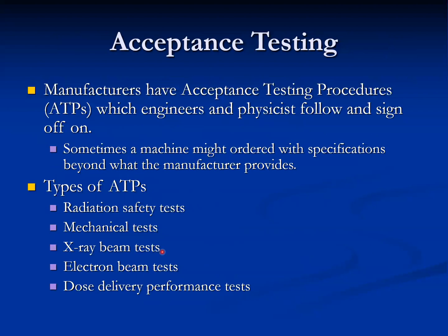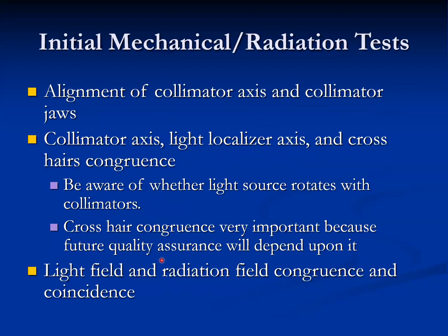The manufacturer has an acceptance testing procedure which engineers and physicists follow and sign off on. Sometimes a machine may be ordered to specifications beyond what the manufacturer provides. The types of ATP include radiation safety tests, mechanical tests, X-ray beam tests, electron beam tests, and dose delivery performance tests.